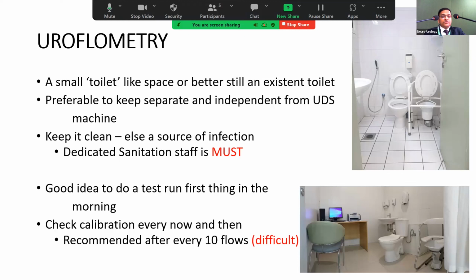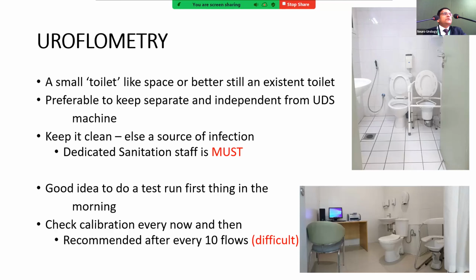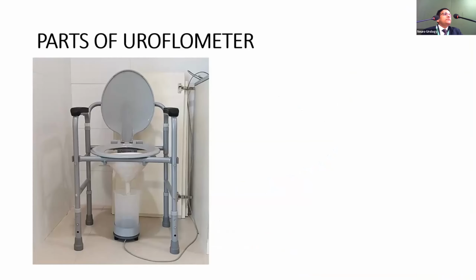It's a good idea to do a test run first thing in the morning, although at times it is difficult. Most of the imported machines have self-calibration, so generally it is not required. But at times it is said that after every 10 voids you calibrate the machine. You can just pour 300 ml at physiological speed, about 15 ml per second, and check the reading of the machine. I'll come to the ICS guidelines on that.